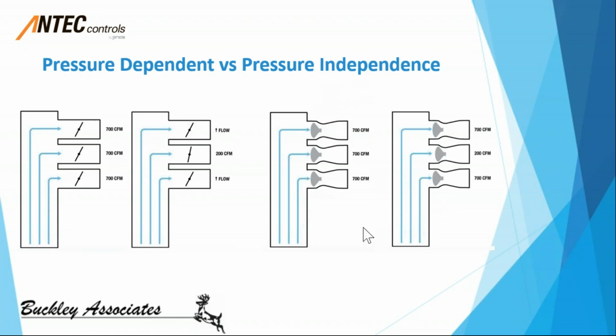In a pressure independent system, which is what we see with Venturi valves, the system has the ability to deliver a specific airflow independent of the pressure in the ductwork. So let's pose the exact same scenario that we just looked at on the left, where this middle damper only requires 200 CFM instead of the 700 CFM. The other two dampers here are going to maintain their same airflow. Even though we blocked this off and reduced it, the flow in both the top and the bottom valves here didn't change. So how does this happen?